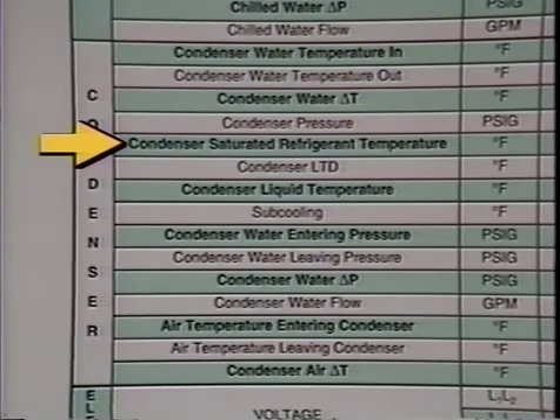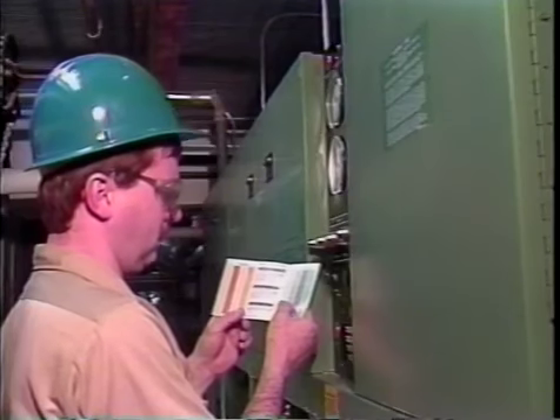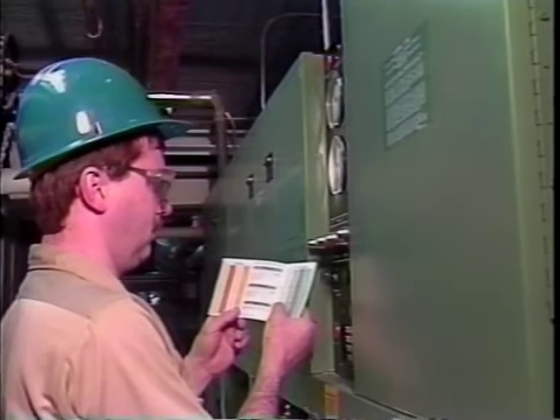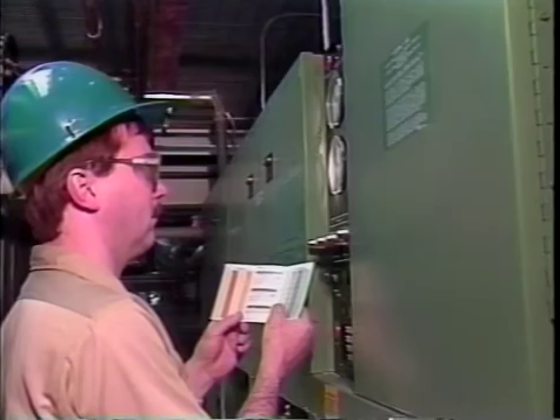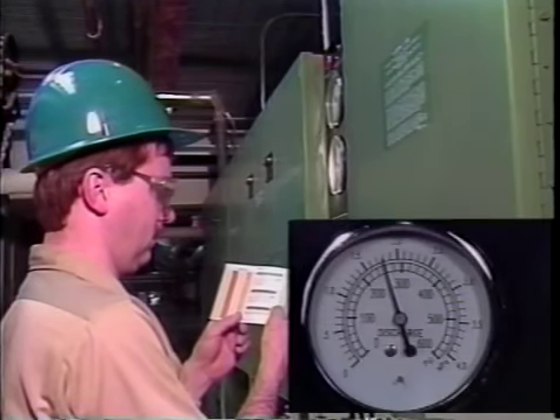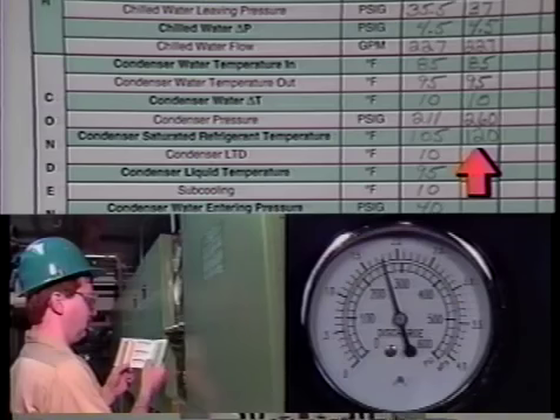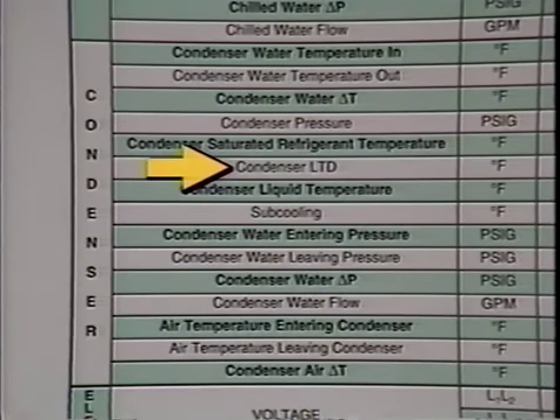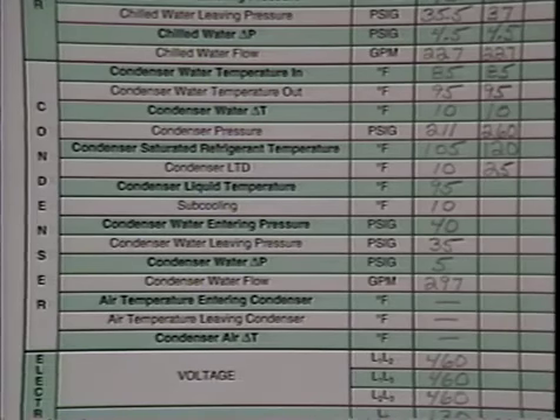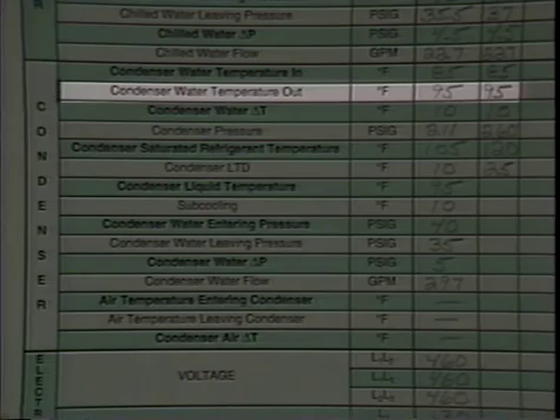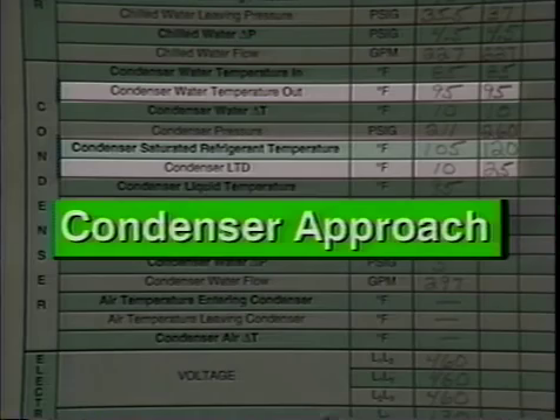Condenser saturated refrigerant temperature. On some chillers, the saturated condensing temperature may be read directly at the control panel. If this is not the case, then the saturated condensing temperature is found by using a pressure temperature chart to convert the condensing pressure to a temperature reading. This temperature is required for determining the condenser leaving temperature difference. Condenser leaving temperature difference, LTD. The condenser LTD is found by subtracting the leaving condenser water temperature from the saturated condenser temperature. This also may be referred to as condenser approach.